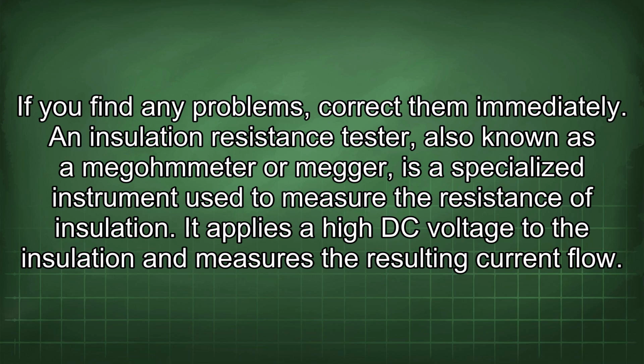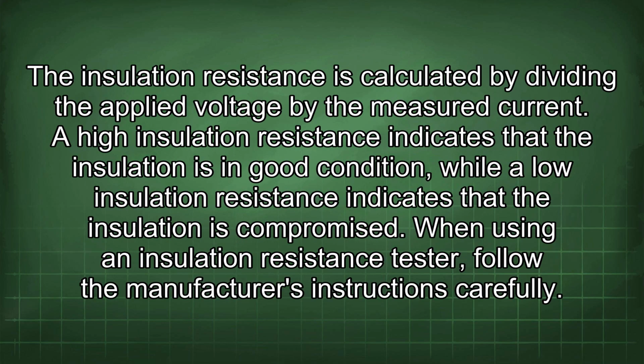An insulation resistance tester, also known as a megohmmeter or megger, is a specialized instrument used to measure the resistance of insulation. It applies a high DC voltage to the insulation and measures the resulting current flow. The insulation resistance is calculated by dividing the applied voltage by the measured current. A high insulation resistance indicates that the insulation is in good condition, while a low insulation resistance indicates that the insulation is compromised. When using an insulation resistance tester, follow the manufacturer's instructions carefully.